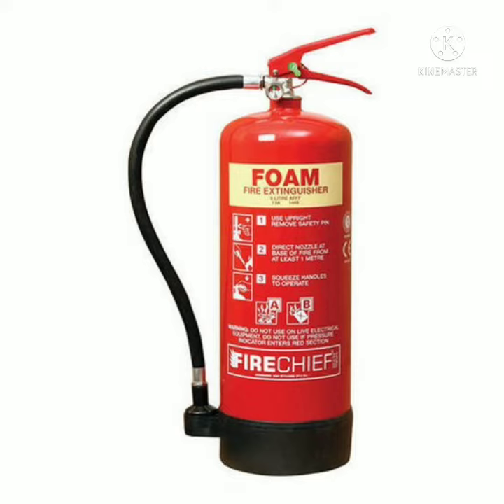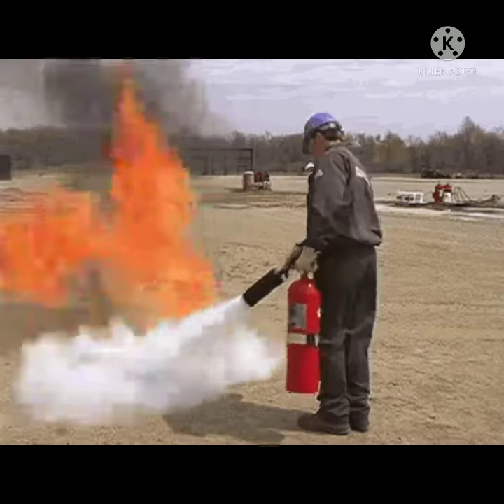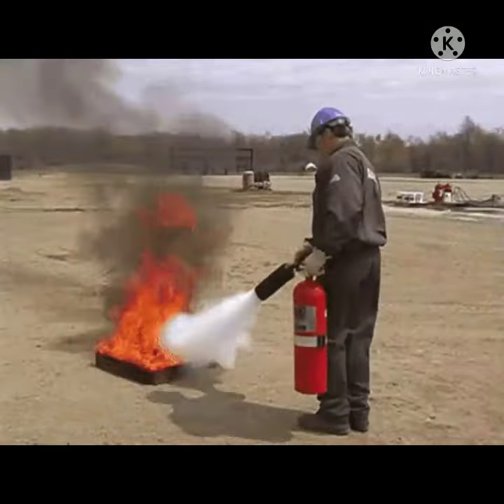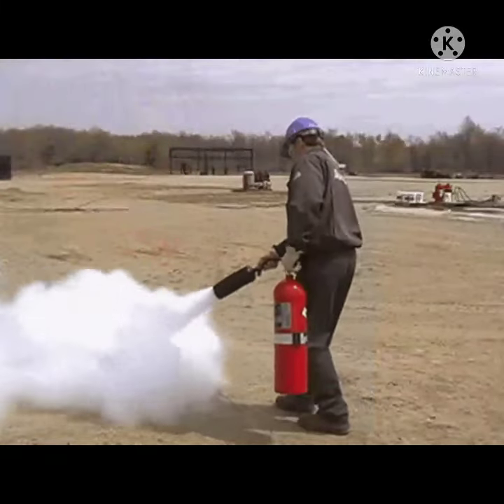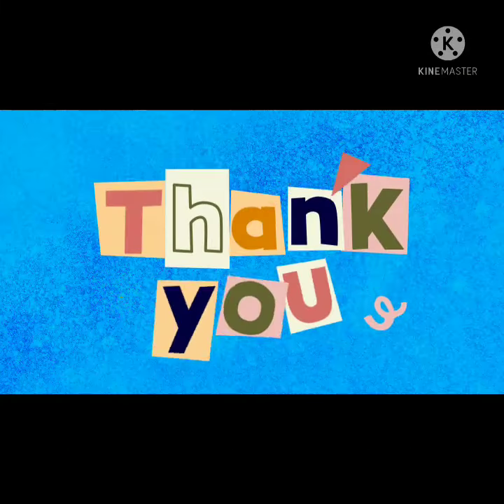Third is the foam type fire extinguisher. A solution of sodium bicarbonate and aluminum sulfate stored in separate sections mix when the extinguisher is inverted. The resulting foam mixture floats on the burning liquid and extinguishes the fire.